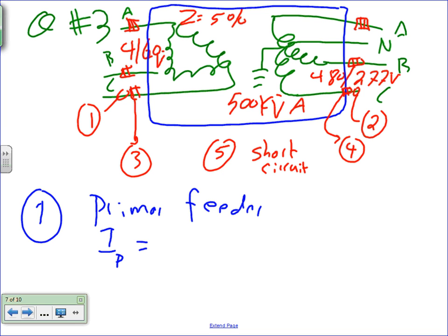Phase A, B, and C, delta Y transformer, solidly grounded right here, you can see, right in here, solidly grounded system, no impedance, nothing. The secondary is 480/277. Okay, let's go ahead and start sizing, guys. The first thing you need to do is take the 500 KVA. I'm doing the primary feeder. Just a quick reminder, the primary feeder is 4160 volts. So that's a medium voltage.